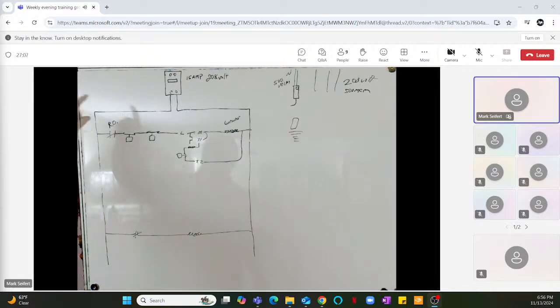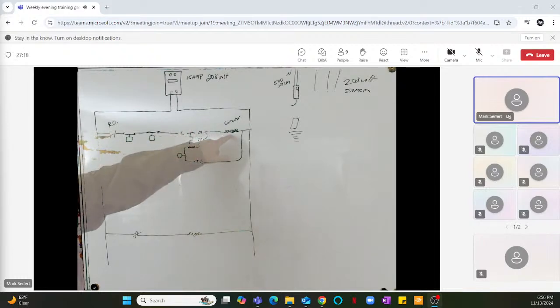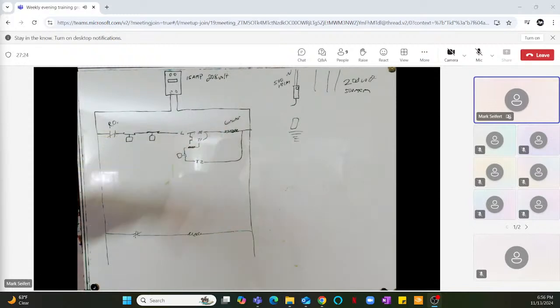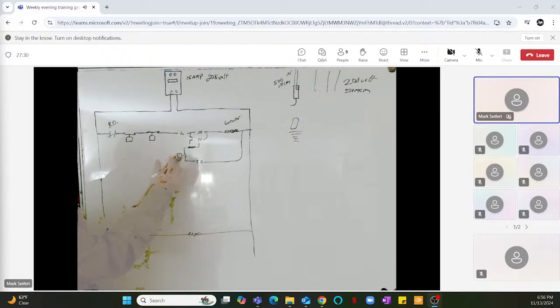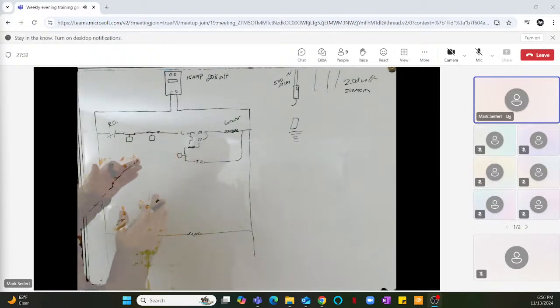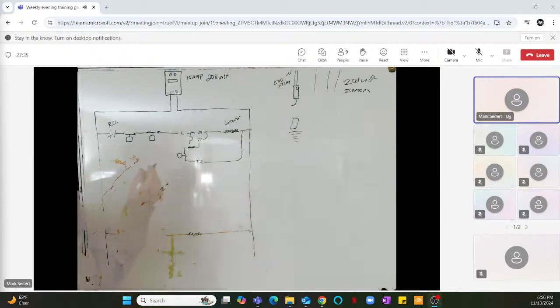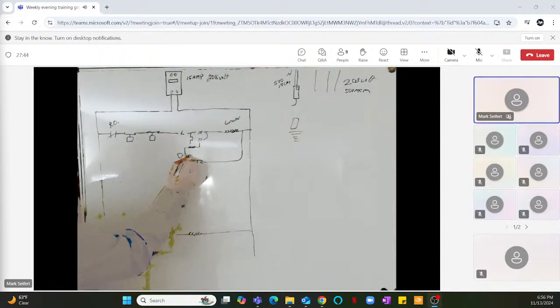So let's just say it calls for the compressor to run. The electricity comes through here, hits L, and it starts the compressor contactor like normal. And then the compressor starts to run. And what does that do here? Inside this pressure terminal, which is basically the two pressure terminals that you have on there, it's a differential pressure. So you're going to have one pushing back, one pushing up. So let's draw the one pushing up. They're fighting each other.